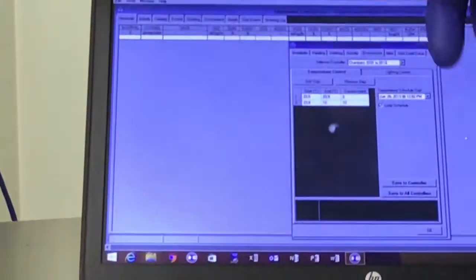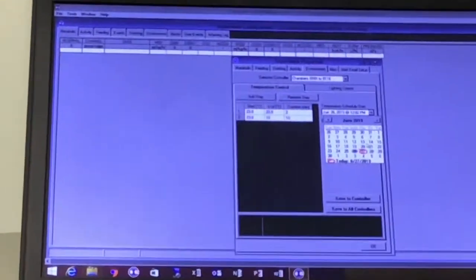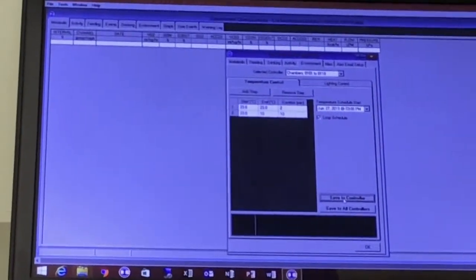Because then it's going to go, okay, when was Thursday? When was Wednesday? What time was it? Wednesday at 5 p.m. And it's going to start calculating from yesterday to your step. But if you do the future, for example, today is June 27, and I want to start something at 3:10, I can enter June 27, 3:10, and nothing happens until then. What time is it? Oh, here, 3:07. So I can do 3:09, and I'll do save to controller. So now it will just run whatever it is, but this schedule will start at that time.